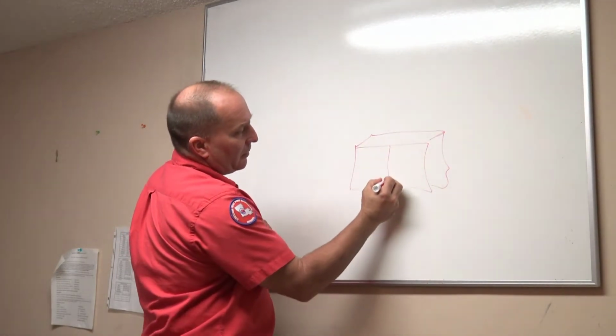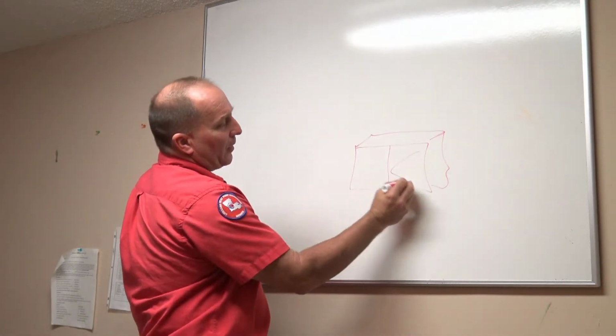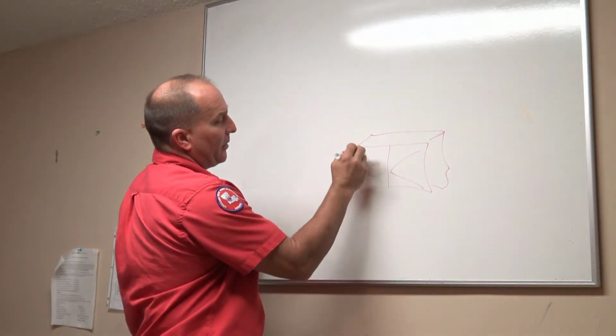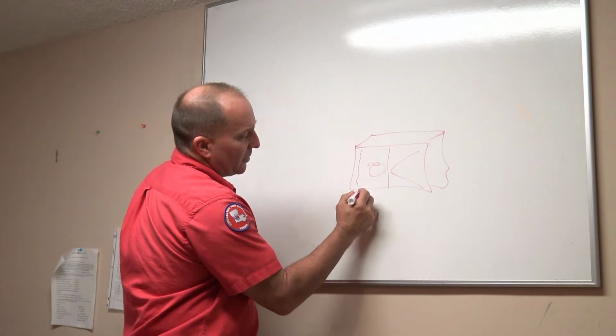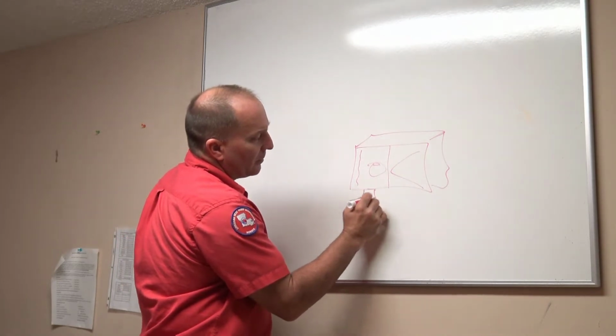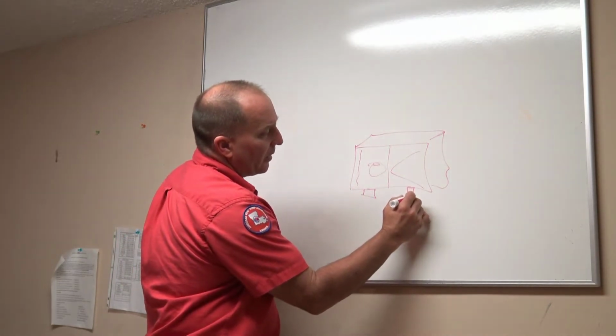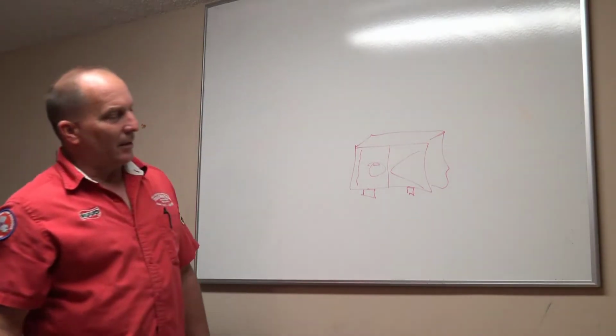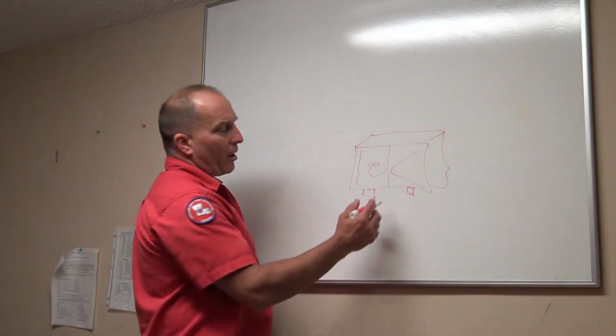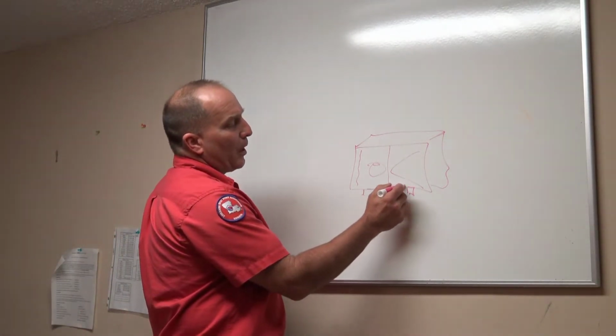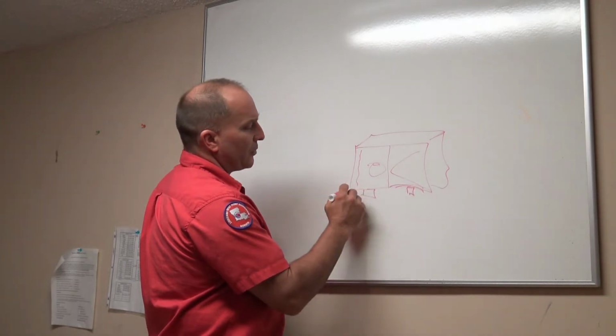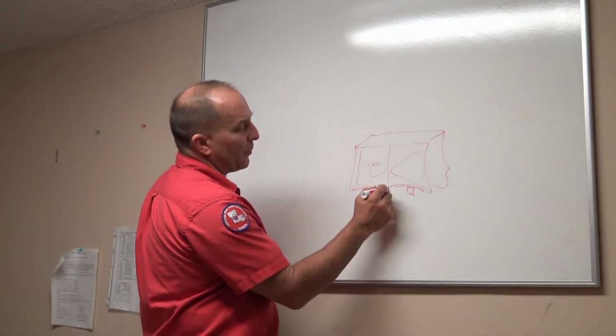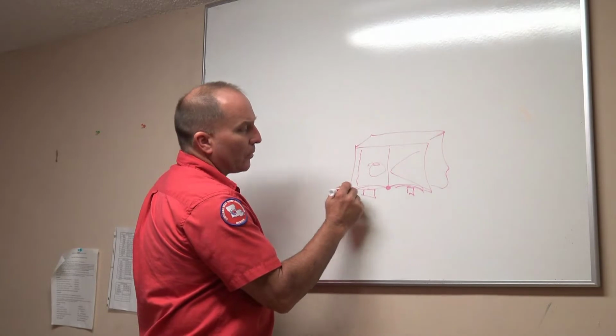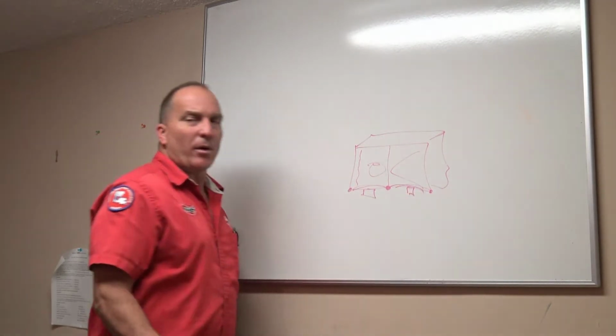So there's a line right in the middle here. Your evaporator coil is here, and your blower motor is here, and your heating elements are here. And then there's the support right here, and then there's the support right here. And they're right in the middle of your air handler, which is going to cause this to bow like that, and this to bow like this, because my support is in the middle on the corners. That's where my support is.